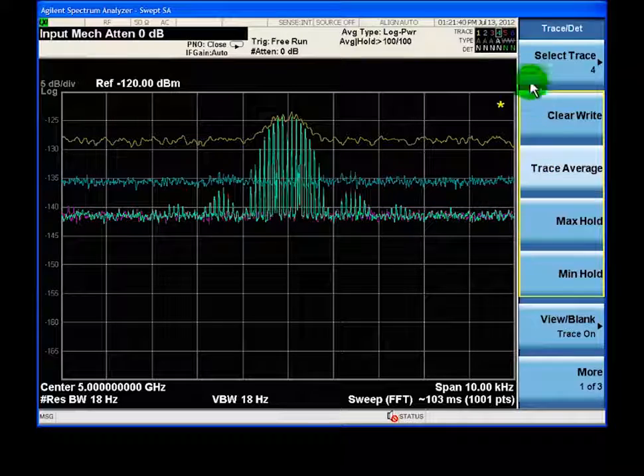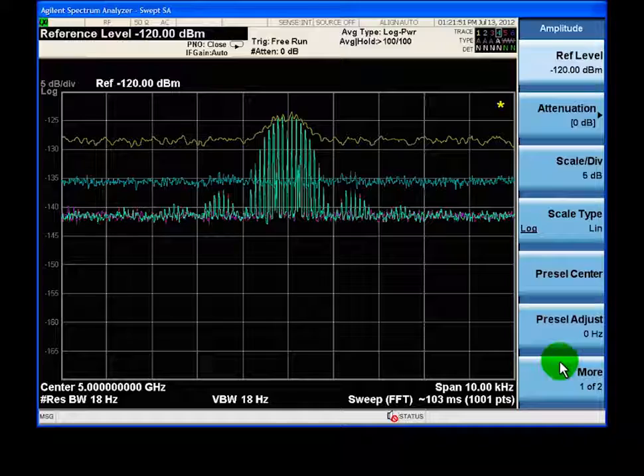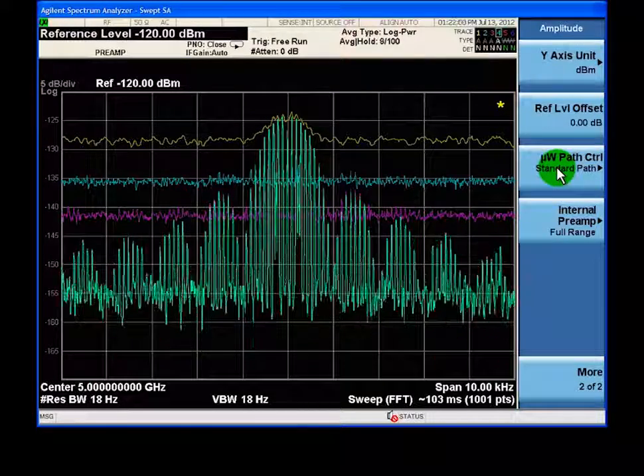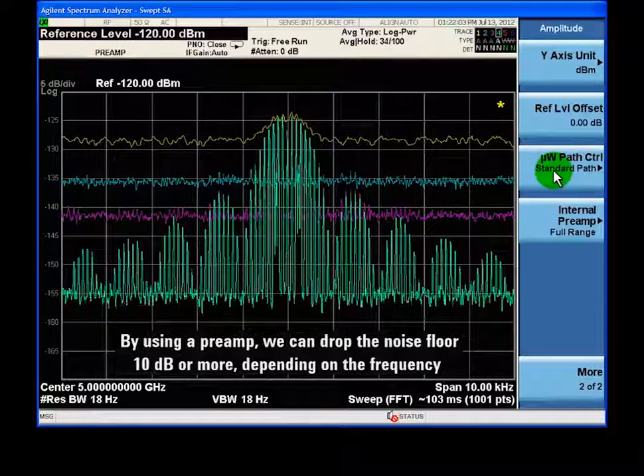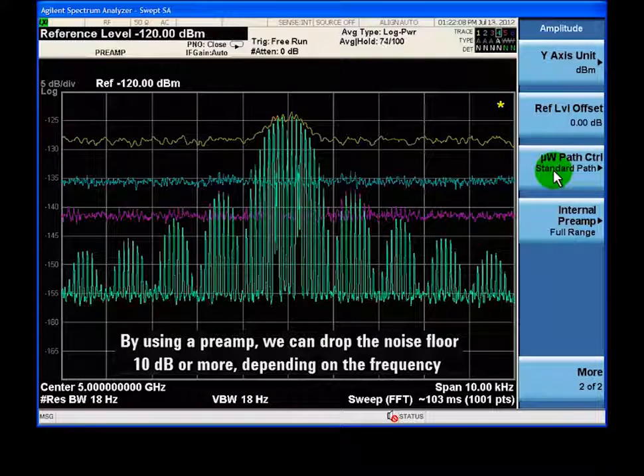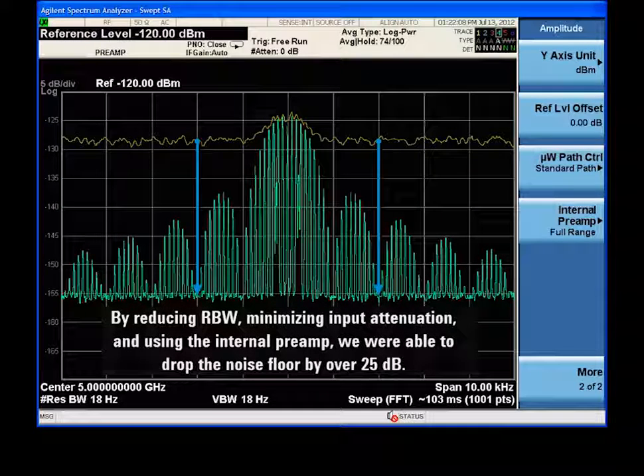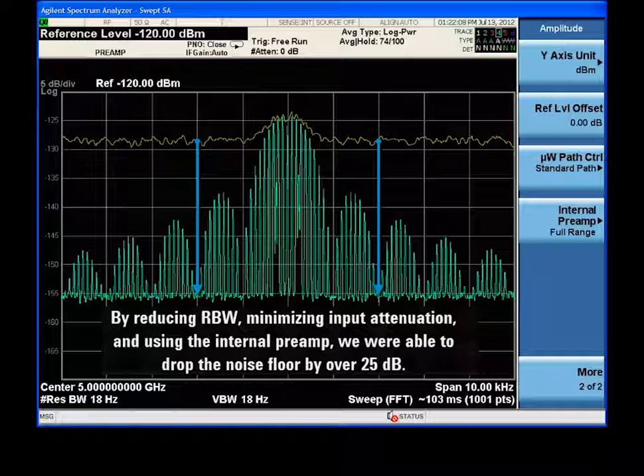Finally, we will use the internal preamp to increase the signal-to-noise ratio. By using a preamp, we can drop the noise floor 10 dB or more, depending on the frequency. By reducing RBW, minimizing input attenuation, and using the internal preamp, we were able to drop the noise floor by over 25 dB.